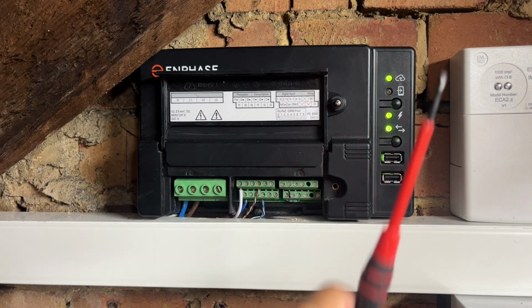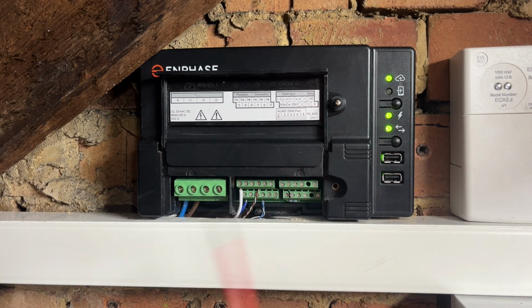That matches up with what I see, because just off the picture here, I have a production CT which is attached to the cable just after the isolator. That cable's travelling along in this ducting and coming up here. And then there's a second CT which this twisted pair is connected to, which is by my fuse box. It's measuring the grid. It's the grid CT, so it's measuring import and export to and from the grid.